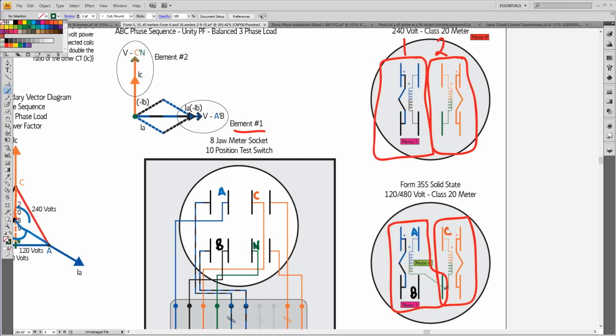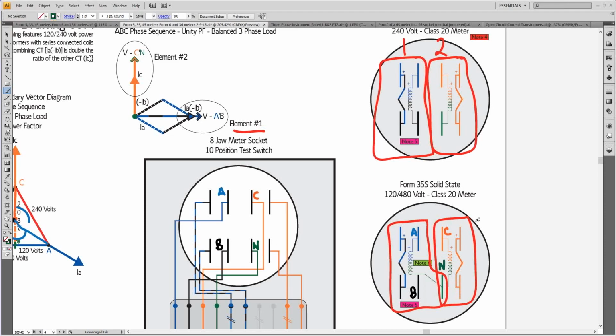This is our neutral, that green. I'm just going to set it right above there. And so as I look at the potential coils, when I plug the 35S into that socket, A to neutral is across the first potential coil. C to neutral is across the second potential coil. And so instead of having A to B voltage like we had with the 5S, I have A to neutral voltage, which is 120 volts.